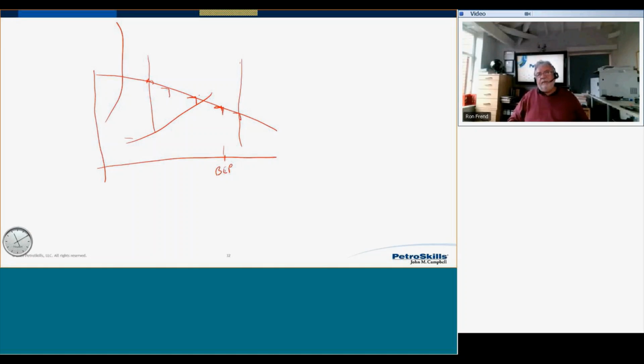If you do need to future-proof your pump, buy a pump where the casing will handle all those sizes, if it's a single stage. And then you can start off by buying a small size impeller, and as time goes on and everything changes, you can swap that out for a bigger impeller. If it's a multi-stage pump, talk to your vendor, show them what you're doing now, show them what you think you're going to be doing in the future. And what they might do is give you a rotor with a few impellers missing. That will put you right in the region for today, but also give you that flexibility for the future.